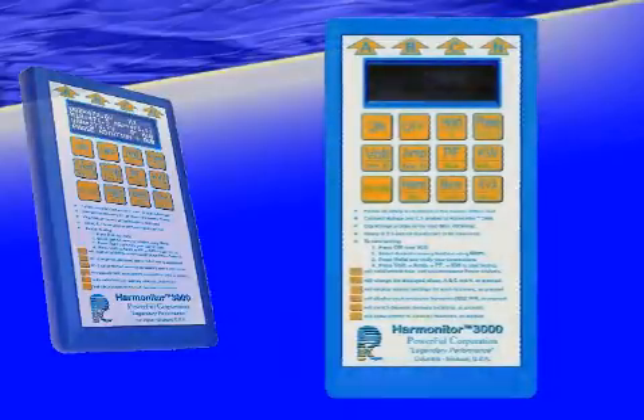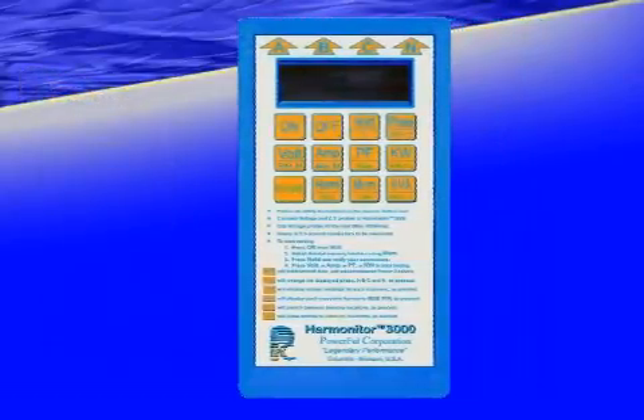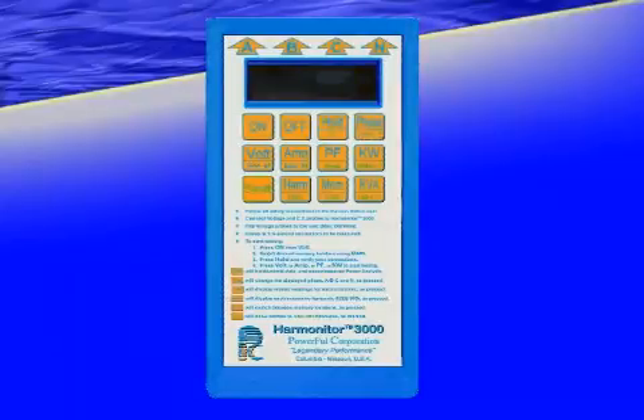The Harmonitor can be powered by batteries or a wall power adapter. The Harmonitor comes standard with three 3000 amp CTs and 4 color-coded voltage clips. If you want to use different CTs than the standard 3000 amp CTs, please refer to the manual. Always connect the CTs and voltage leads to the Harmonitor before attaching them to a load. When attaching CTs, make sure you connect them on the correct phase and in the correct direction, indicated by the arrow pointing toward the load. Also, make sure the voltage leads are connected to the proper phases.